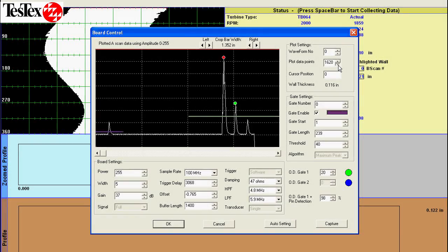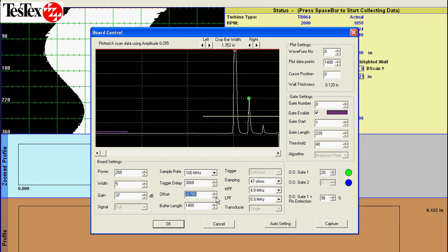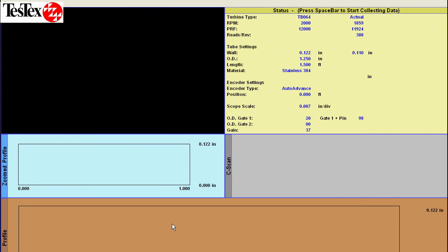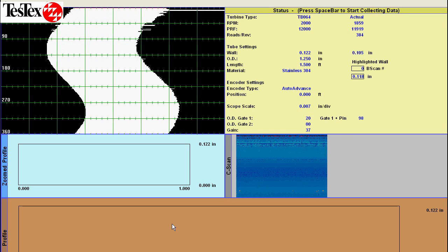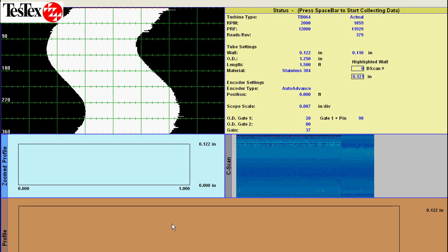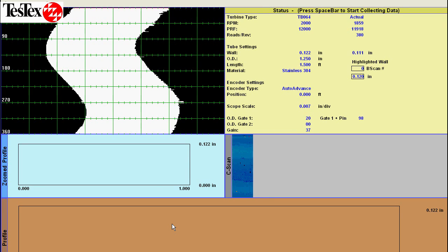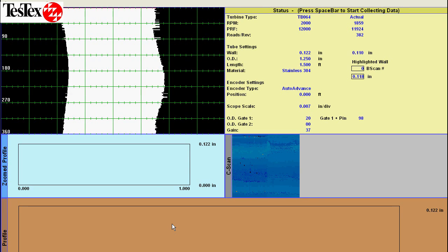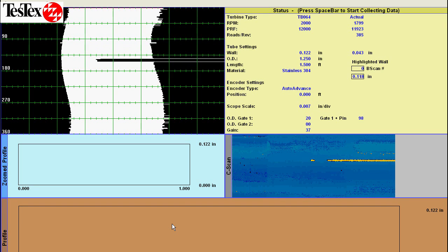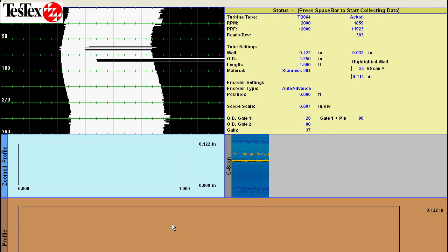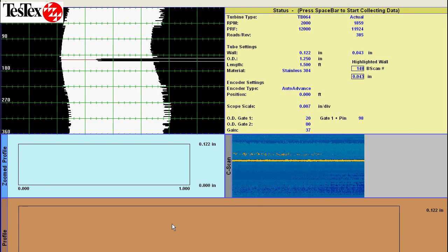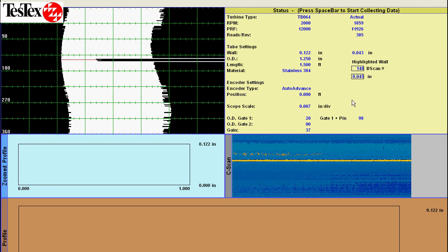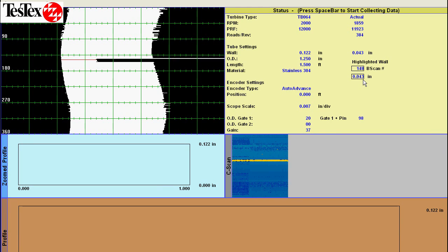Here you can see the data collection screen. We have full control of all settings and can manipulate the data even during acquisition to get the most accurate reading. You may notice we do not have a pin signal. This is because our software is designed to gate it out and see the tube wall behind it. Our system also allows you to save the data to the Helix for later retrieval.